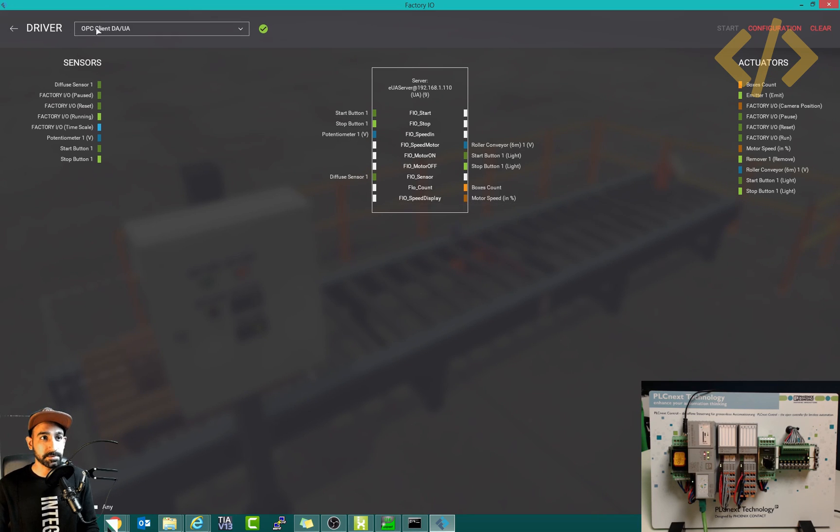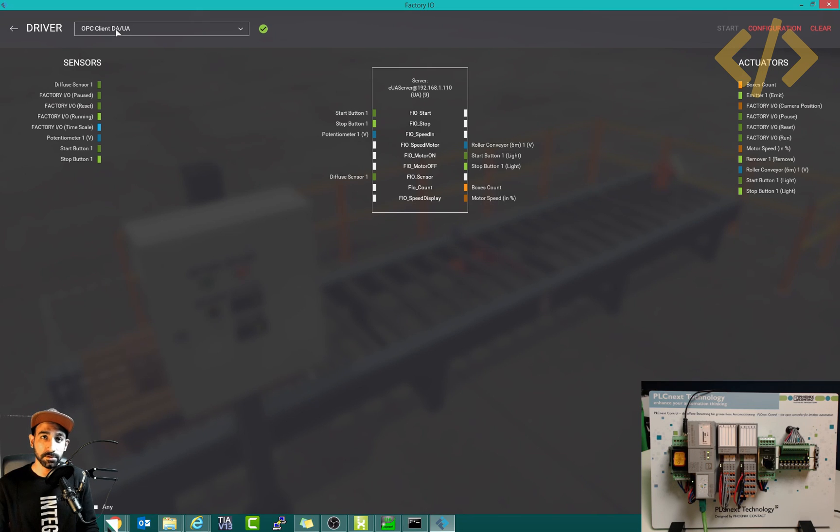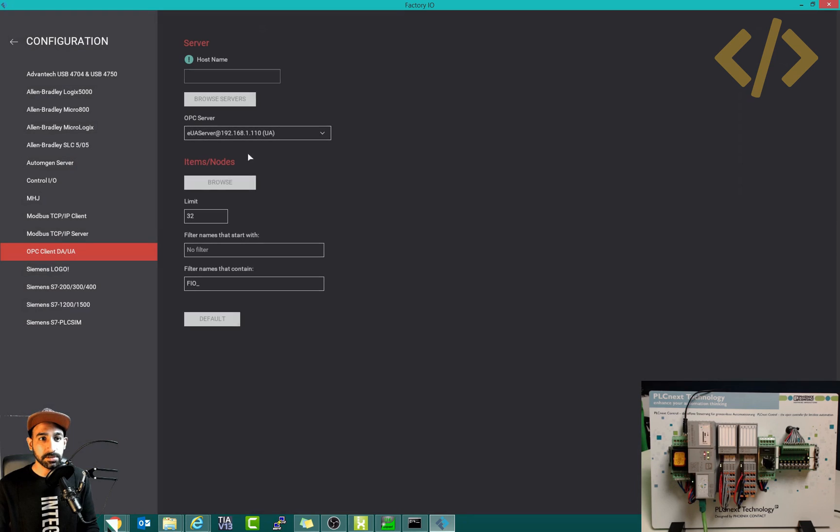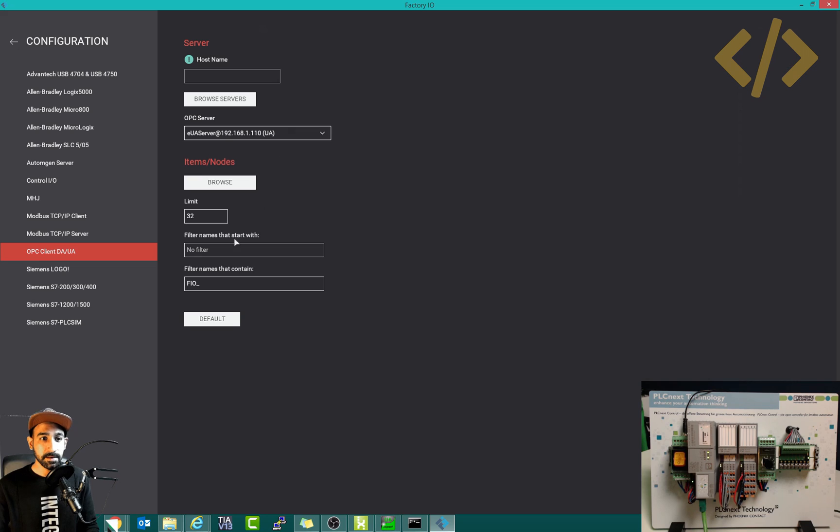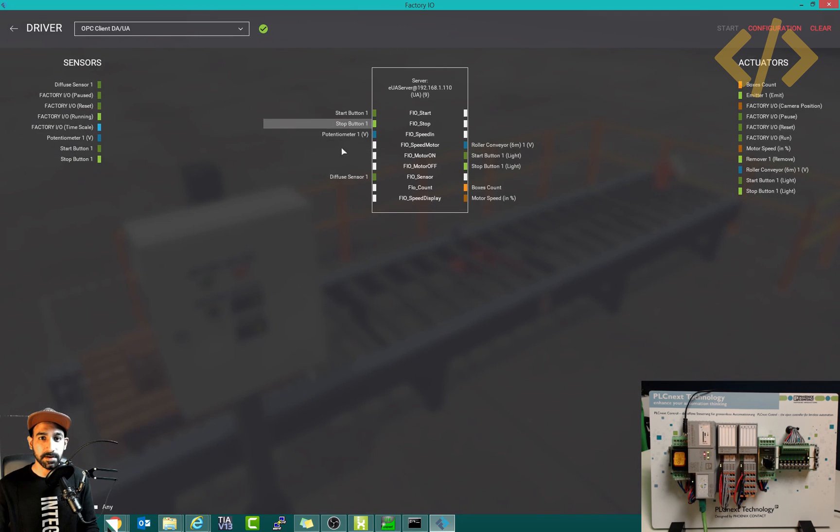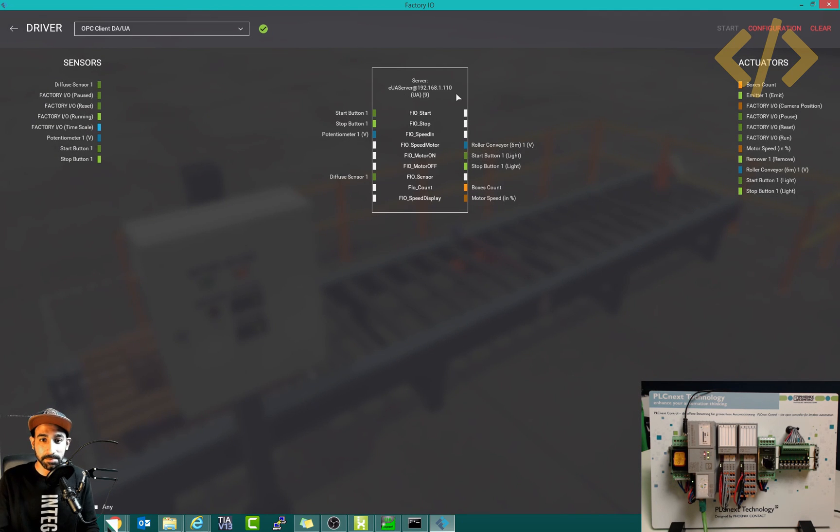The drivers I'm using is OPC client, like I've shown you before with Node-RED and UAExpert. In the configuration, I have entered the OPC UA server which was defined in my PLCnext, and I'm using a filter with the tags FIO underscore. This makes it easy to find the tags, otherwise there's so many tags coming up.